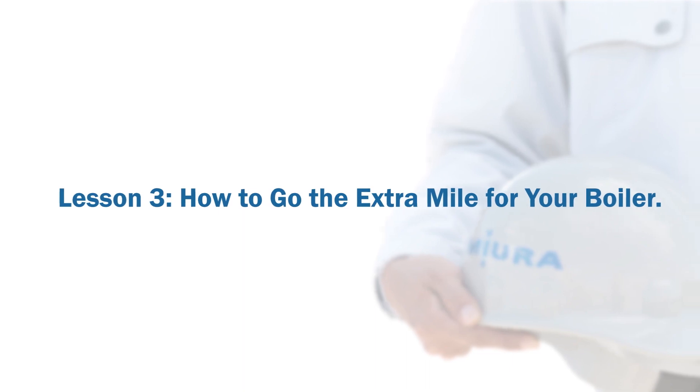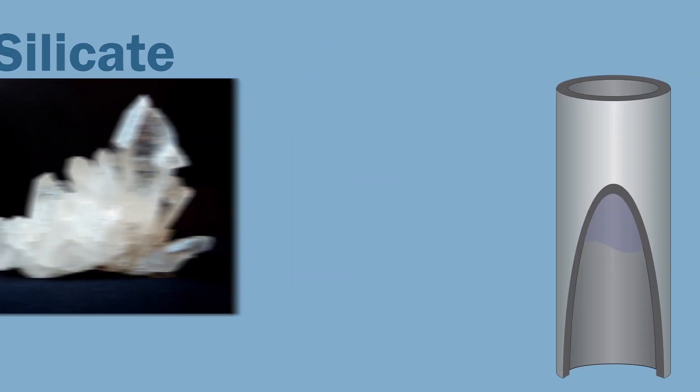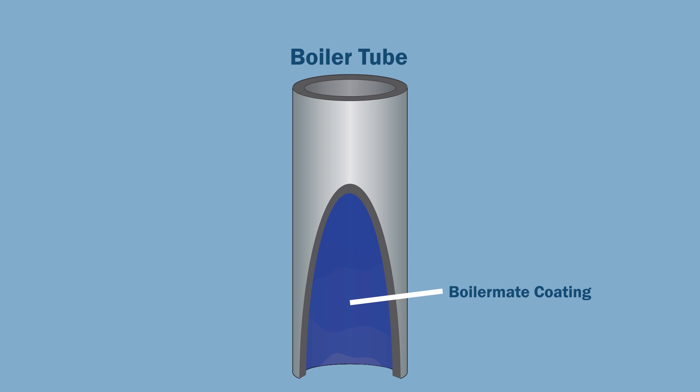Lesson three: how to go the extra mile for your boiler. Boiler treatment chemicals are used to inhibit corrosion within the boiler. Miura's patented Boilermate chemical treatment is a perfect pair with our water softeners and colorimetry system. The main ingredient of Boilermate is silicate, a corrosion inhibitor. Silicate is a naturally occurring material ideal for water treatment in Miura's once-through boilers. Water tube corrosion can be controlled by balancing the amount of silicate in the water and the corrosive ions.